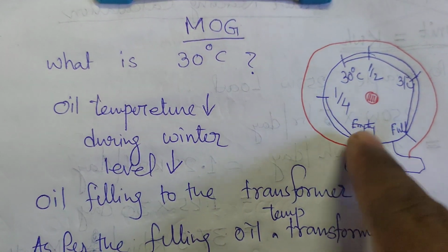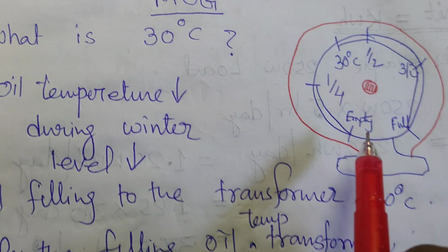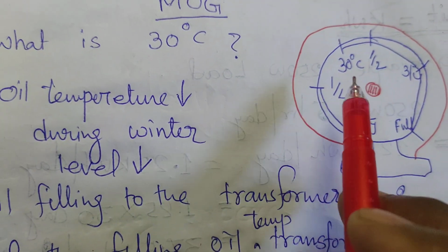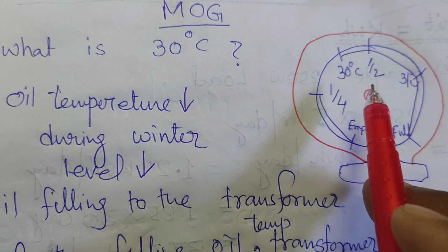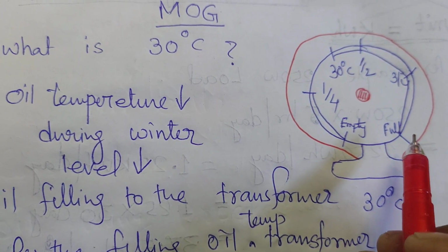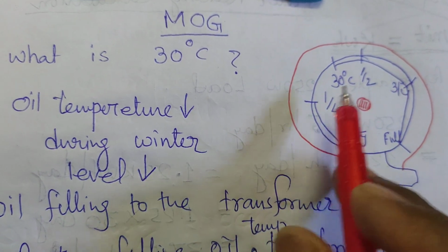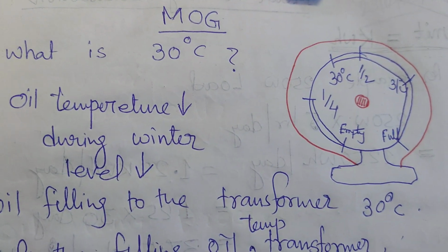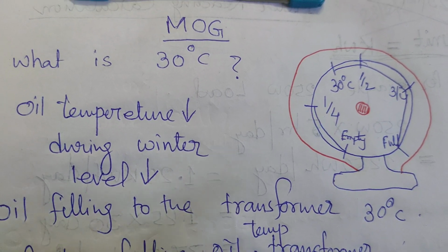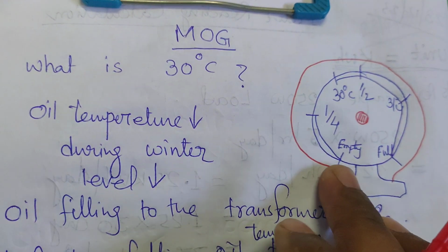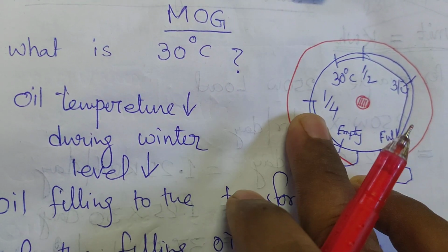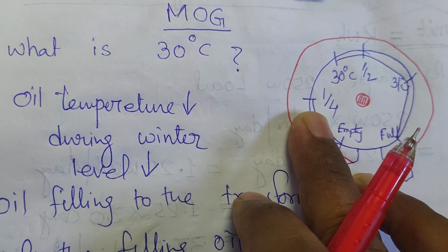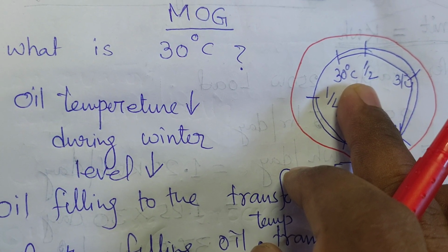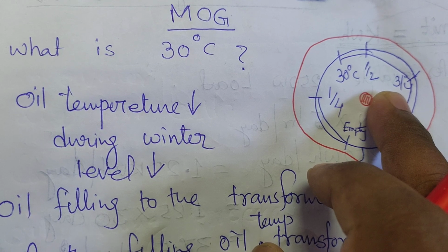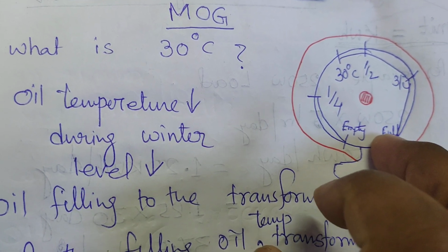And if you see the dial of the gauge, you can see empty, 1/4, 30 degrees Celsius, half, 3/4 and full. These indications just depend on the position of the oil inside the conservator tank. If it is empty, that means no oil is present inside the conservator. If it is 1/4, then 1/4 of the conservator is filled with oil. If it is half, that means half of the conservator is filled. 3/4 means 75% filled, and full means 100% filled.